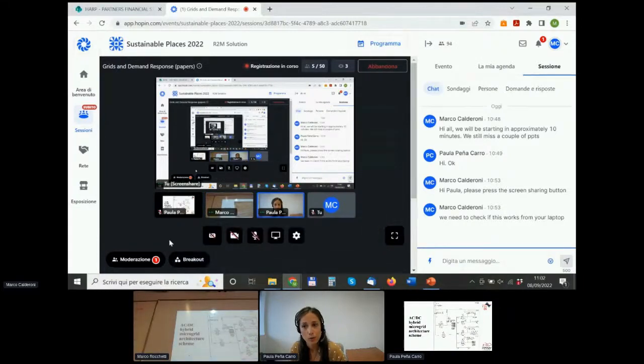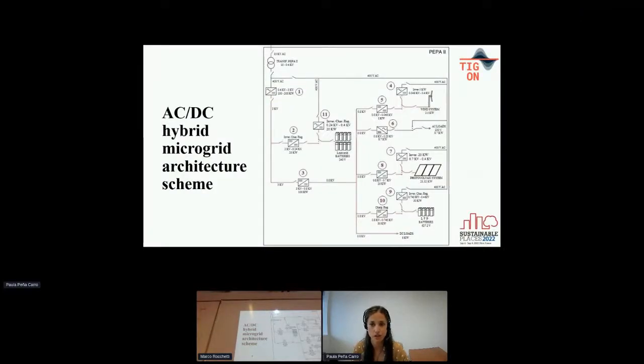In this slide we can observe the hybrid microgrid architecture at CEDER. CEDER's general grid is an AC medium voltage power grid. This arrives at the PEPA 2 transformation center and is reduced from 15 kilovolts to 400 volts. The 400 volt grid is the AC grid we see in blue. It enters the solid-state transformer to convert the AC grid into a 3 kilovolt DC grid. Here starts the DC grid, shown in red.